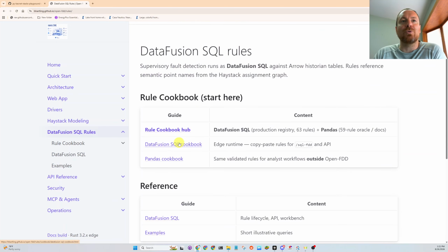So what I also do during some of these tests is I have a synthetic data set, where it's just like an hour's worth of data, and then it's very obvious, like a sensor fault. So it's just a confirmation, like a very rigorous, easy confirmation that the fault equation works. And then it also snapshots a component of time. So what we want to do in fault equations is capture the lapsed time that we've been in a fault mode. And some of it's useful for energy engineering calculations.